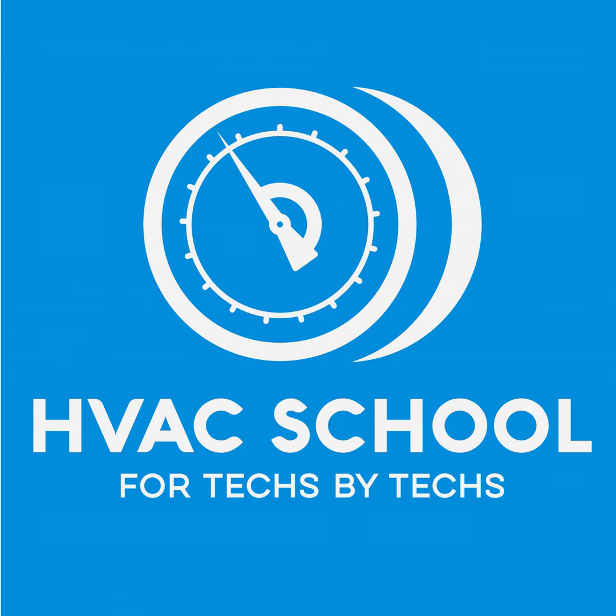So instead of piping up your TXV on your air handler, I pipe up my electronic expansion valve to my air handler. And then I just add a control box to it. That control box acts just like one of the other indoor VRV units. I have a couple pipe thermistors. I got a return air thermistor. And then I hook up my navigation controller or my thermostat to it. So now I've taken that third-party air handler. Again, it doesn't care what brand it is. It just cares that there's a refrigeration DX coil in there. That's going to act and run in unison with the rest of my VRV equipment, like any other unit.